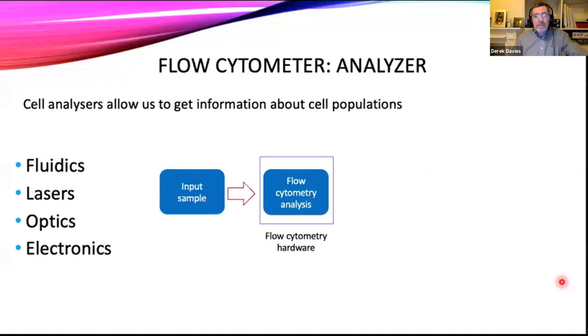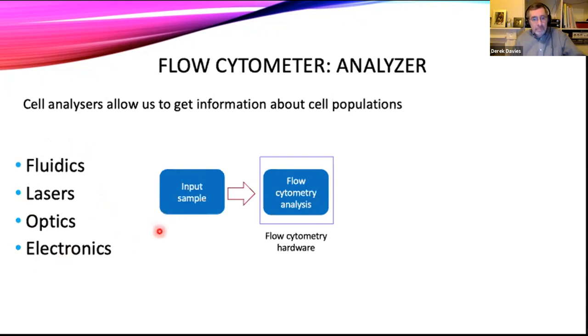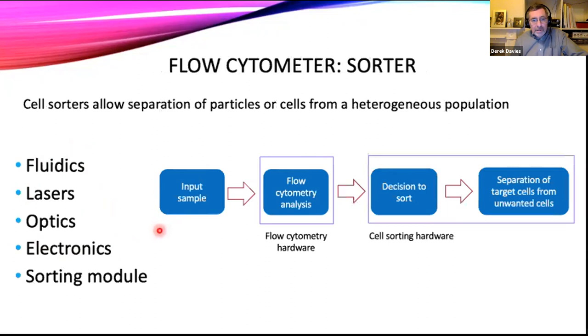Most of us are familiar with flow analyzers. No matter who we buy our flow analyzer from, it will have the same basic components: a fluidic system to take our cells through the machine and hydrodynamically focus them for single cell measurements; one or more lasers to excite the fluorochromes; an optical system with long-pass, short-pass, and band-pass filters to separate light; and an electronic system to capture and quantitate that light. A cell sorter also has all of those components — it just has an extra part: a sorting module.